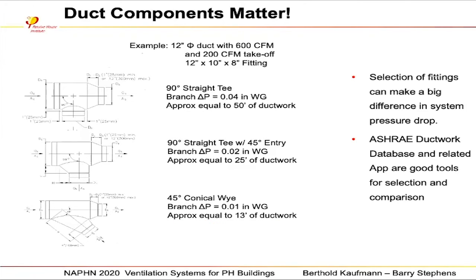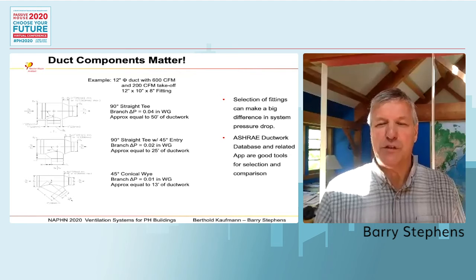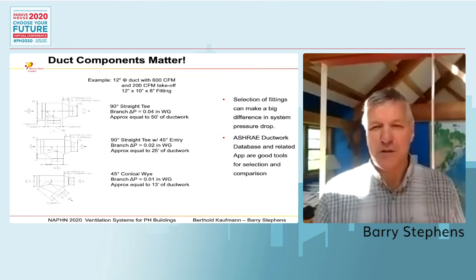This is another example very quickly. This is where you have a T connection, and you can see the difference here. The top is just a straight T at 50 feet of equivalent of ductwork. If you put a T with an entry branch into it, they call it, it's 25 feet, so half as much. If you use a Y, it's 13 feet of ductwork. So you're looking at about a third as much static. And again, you may have many of those in a system, and then it can all add up. So it really translates into increasing the static in the system, increasing the fan power required, and in some cases, it could be the difference between actually having the unit be able to deliver the amount of air that you promised, which we're going to talk more about.